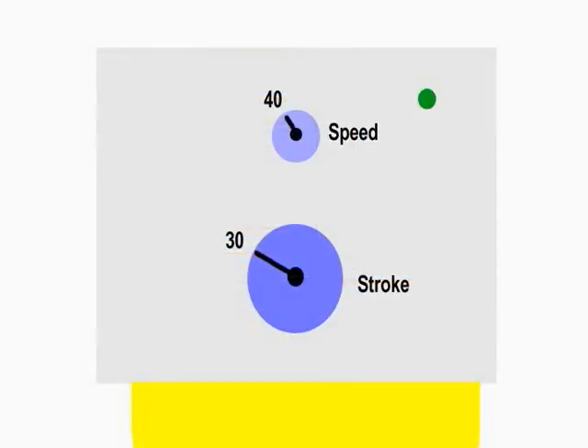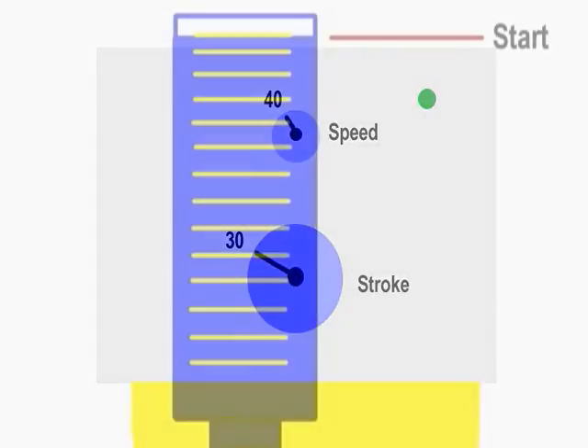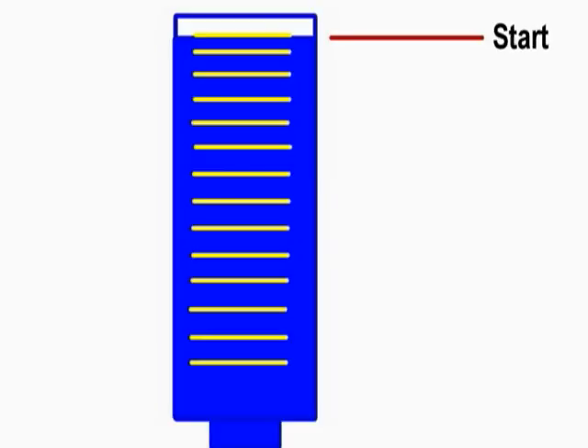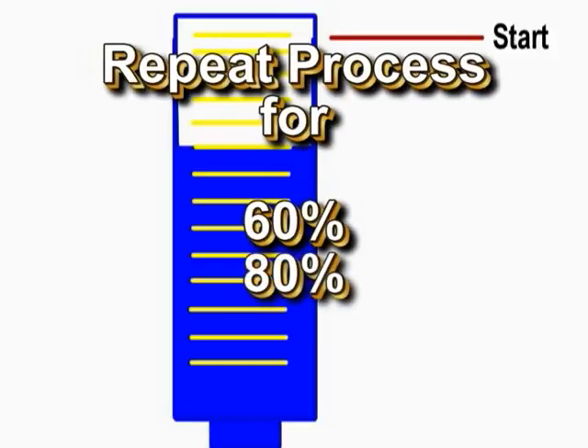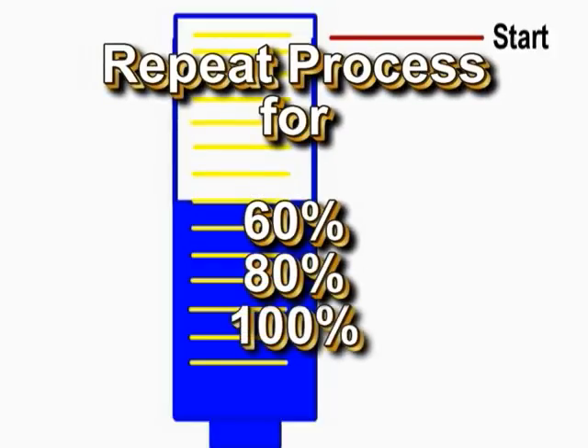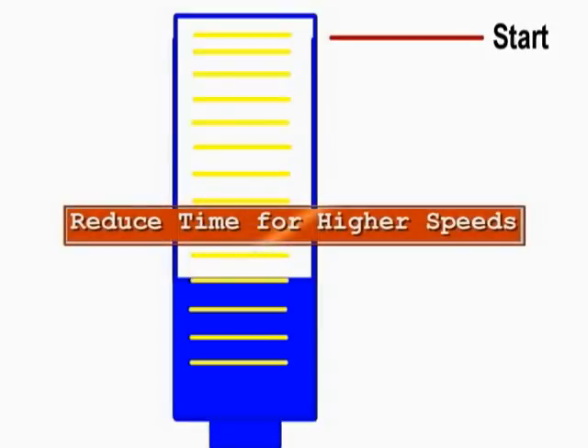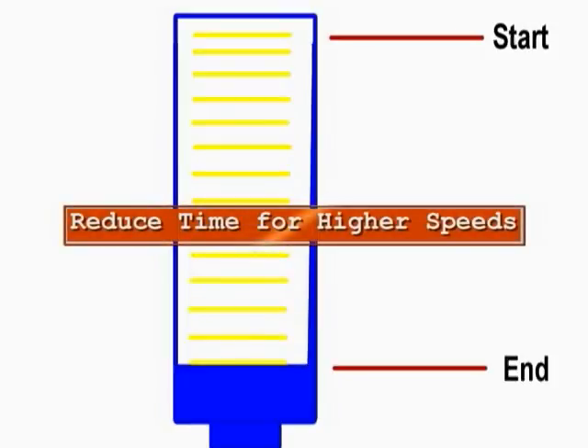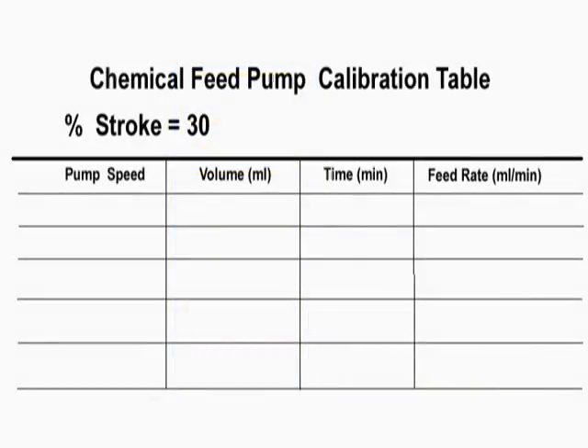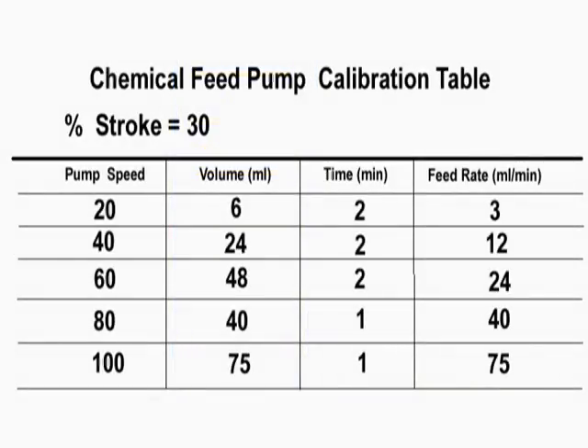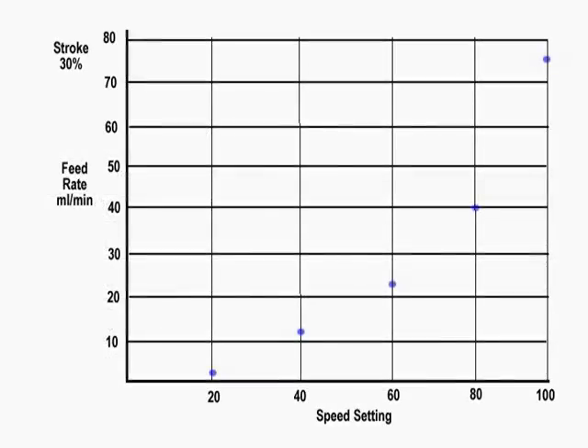Next, set the pump speed to 40 while keeping the stroke at 30%. Refill the calibration tube and time for 2 minutes again. The process should be repeated for 60, 80, and 100% speeds. The time can be reduced to 1 minute for the higher speed settings. The results should be recorded on a table and graphed like the example shown here. By drawing a line through the points, the operator can illustrate the delivery characteristics of the pump.